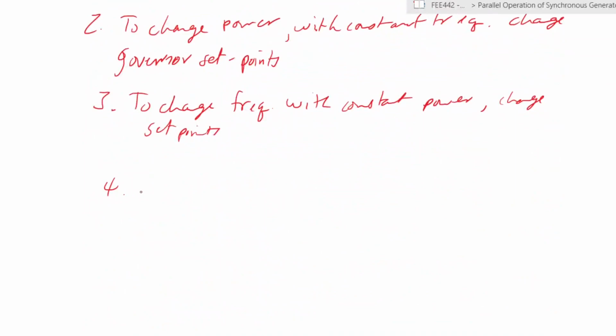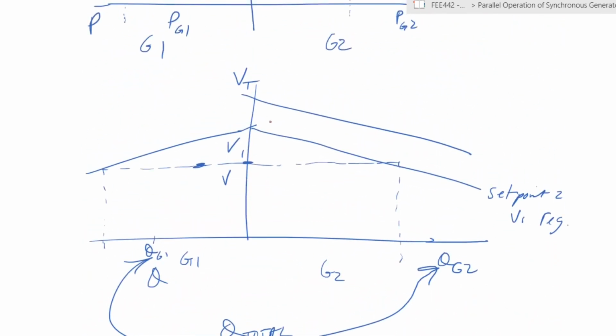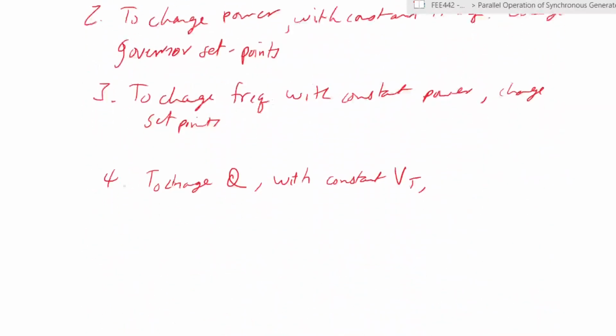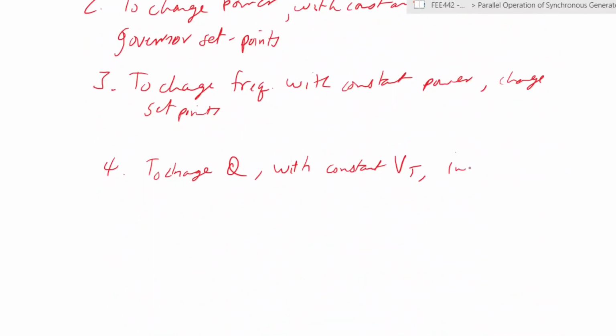Number 4, in order to change reactive power, Q, with constant voltage, VT, you can increase the value of the set points, and you increase on one and you decrease on the other in order to match the two. Increase, decrease. We will demonstrate all of this shortly.